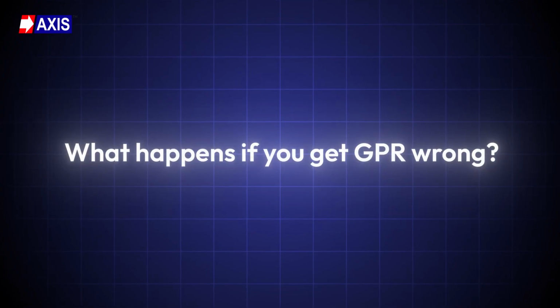But what happens if you get it wrong? If GPR is too high, the voltage gradients across the substation yard exceed safe limits. Touch and step potentials become hazardous and the protection systems can malfunction. Any telecommunications or control cables leaving the substation carry that elevated potential with them, and this creates risks far beyond the substation boundary. So how do you fix it?